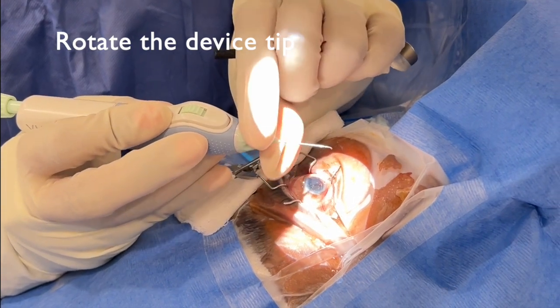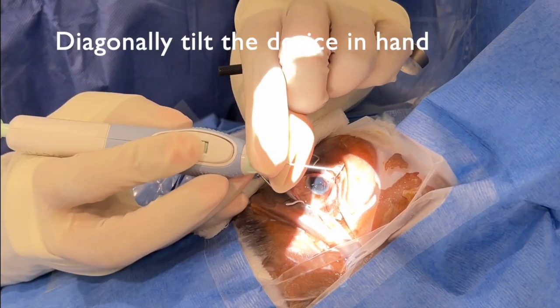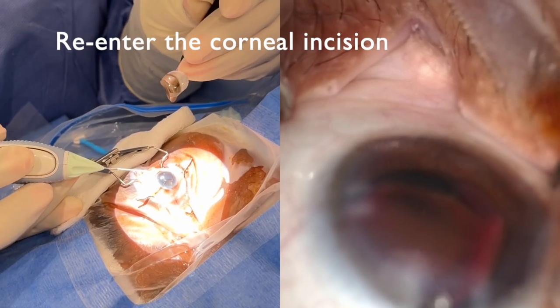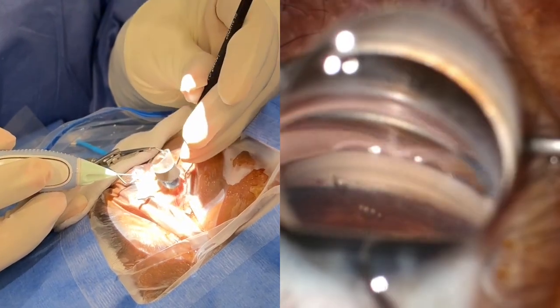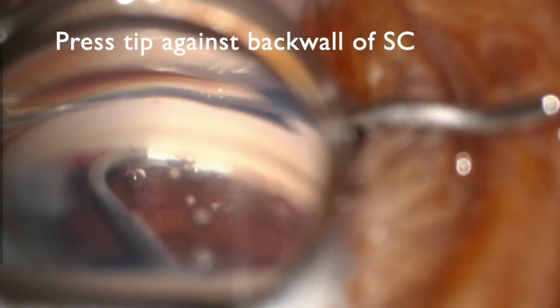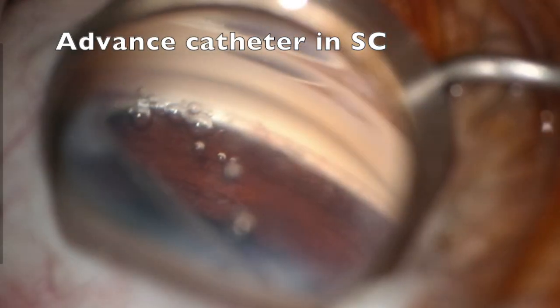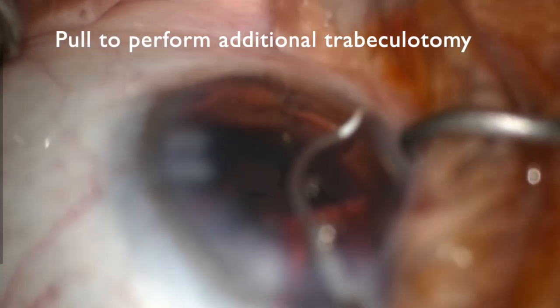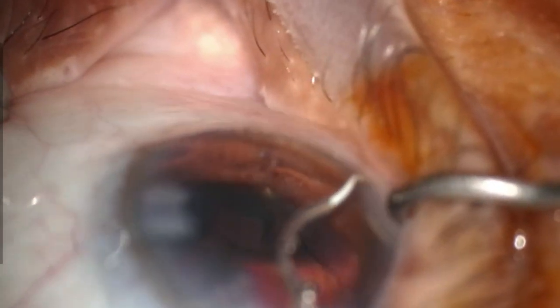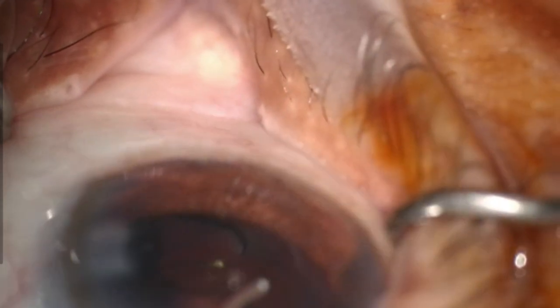To do this, rotate the device tip to the appropriate position and diagonally tilt the device in your hand. Then reinsert the tip through the corneal incision. Apply the gonioprism and then advance the tip towards the trabecular meshwork. You can enter through the opened area of Schlemm's canal by pressing the tip against the back wall of the canal. Once the tip is in the canal, advance the catheter by rotating the wheel. Here, I pull to perform additional trabeculotomy. Again, removing my gonioprism and pulling down towards the angle.